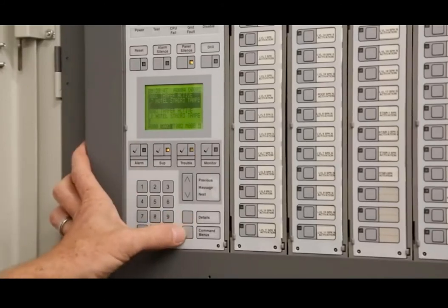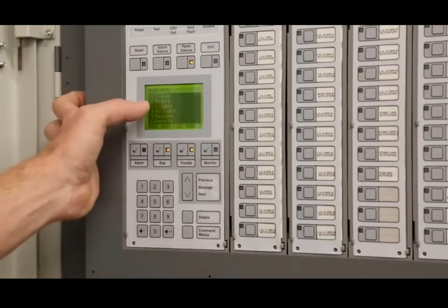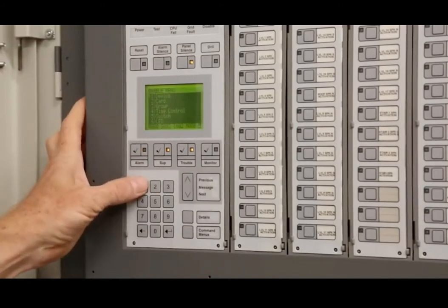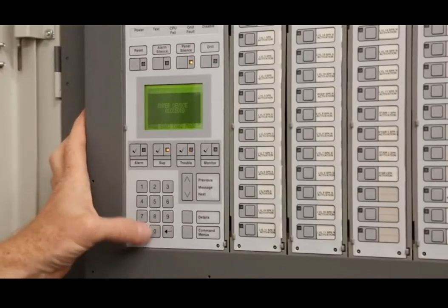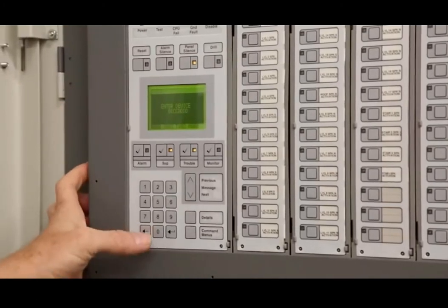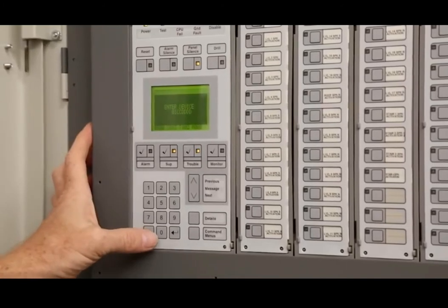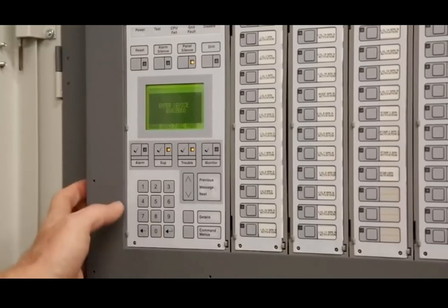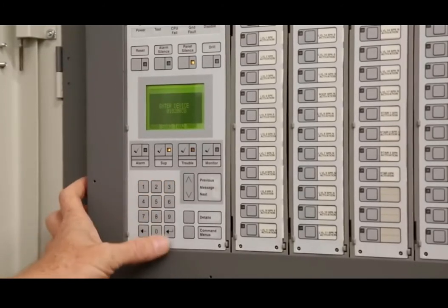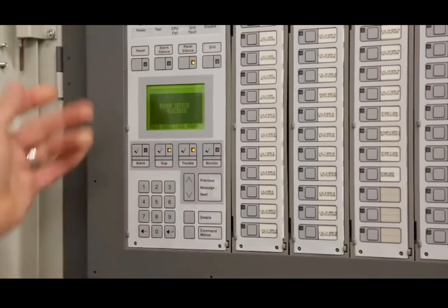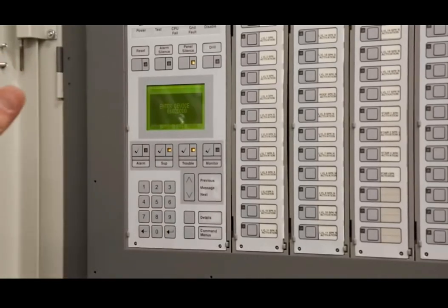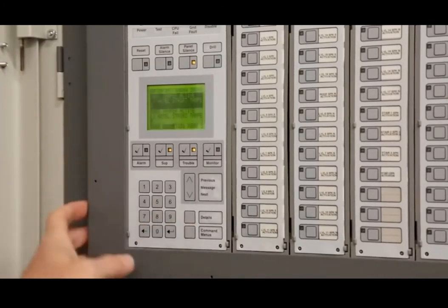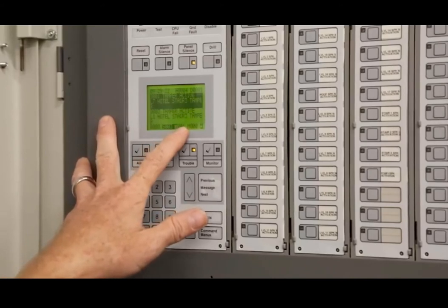To re-enable it again, just hit the command menu again, go into enable, which is number 2, and it all prompts you on there. Device, and again, just put that number back in. Remember, you've got to fill all the characters up. So if it's card 2, you have to put 02 in there, and then fill in the first 4, and then it was 38. Hit enter. Right now, it didn't ask for a password because that password's held in there for 15 minutes. So if you came back later on, you'd have to put the password back in. If you notice, we're back down to 1 trouble again.